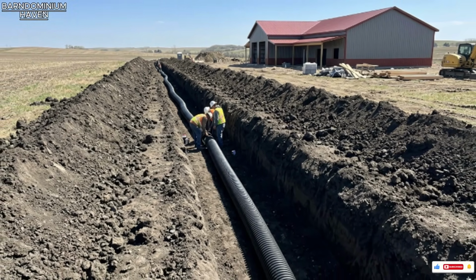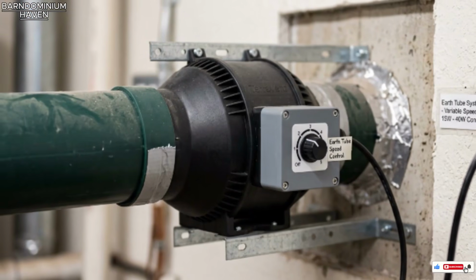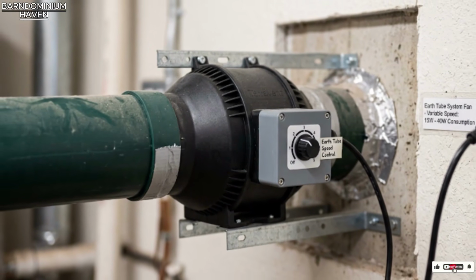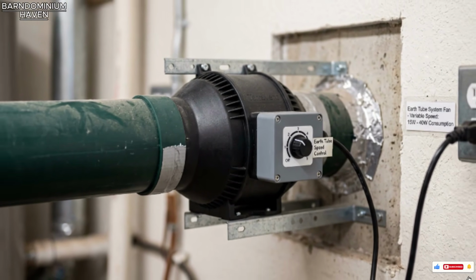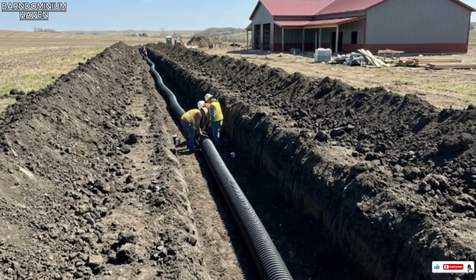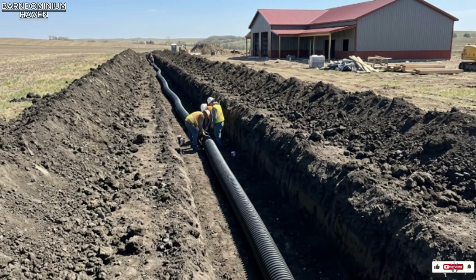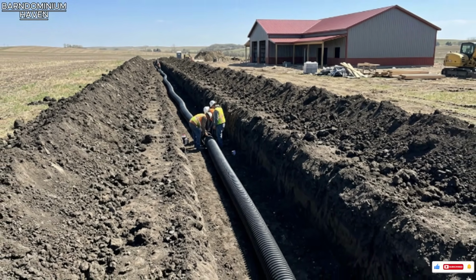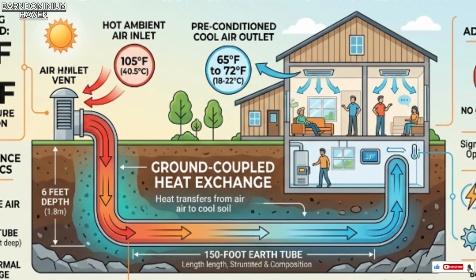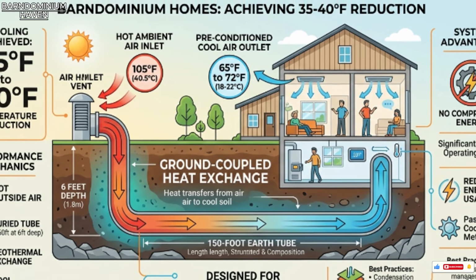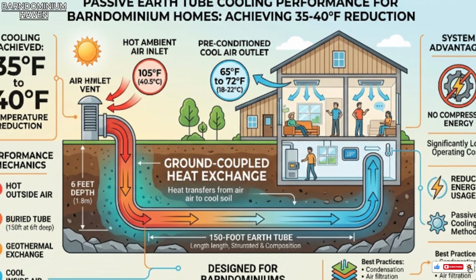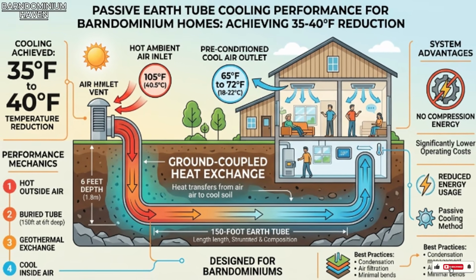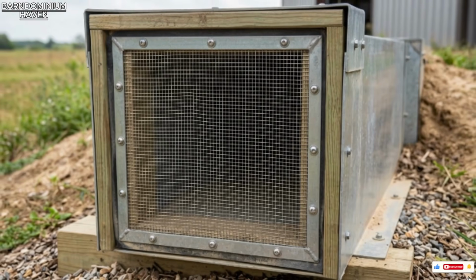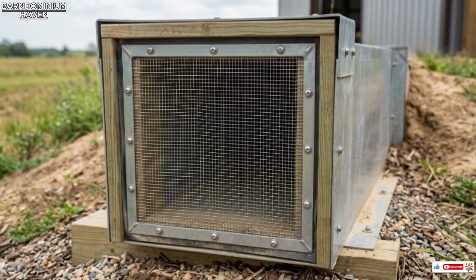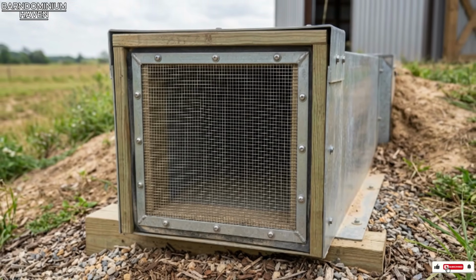When 105-degree outdoor air is drawn through a pipe buried at 6 feet over the length of the pipe run, typically 100 to 200 feet, the air exchanges heat with the surrounding soil, arriving at the building's air intake at approximately 65 to 72 degrees, 35 to 40 degrees cooler than when it entered the pipe, without consuming a single watt of compression energy. The only electrical consumption in a passive earth tube system is the fan that draws air through the pipe.